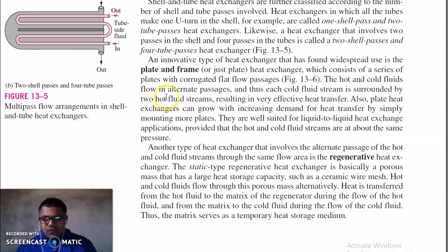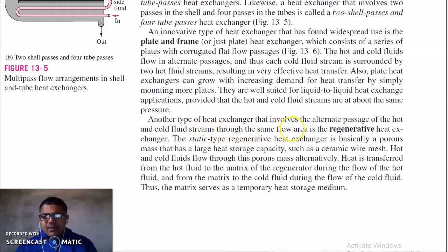The hot and cold fluids flow in alternate passages, and thus each cold fluid stream is surrounded by 2 hot fluid streams, resulting in very effective heat transfer. Also, plate heat exchangers can grow with an increasing demand for heat transfer by simply mounting more plates. They are well suited for liquid to liquid heat exchanger applications, provided that the hot and cold fluid streams are at about the same pressure. Another type of heat exchanger that involves the alternate passage of hot and cold fluid streams through the same flow area is called a regenerative heat exchanger.